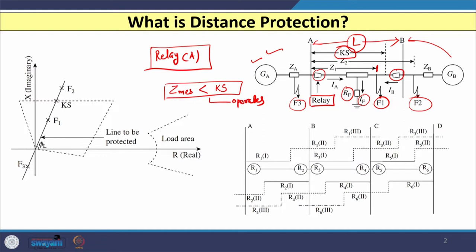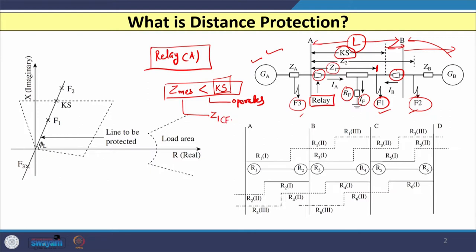Each distance relay has three zones. The first zone covers 80 percent of the line length and is the instantaneous operation zone. The second zone is a time-delayed zone covering the remaining 20 percent plus 50 percent of the adjacent line. The third zone is also time-delayed and covers the end of the next-to-next substation. For fault F1, measured impedance Zmes is less than Ks, so the relay operates.